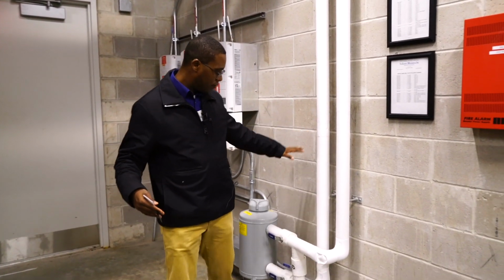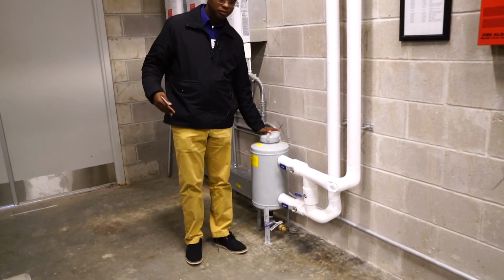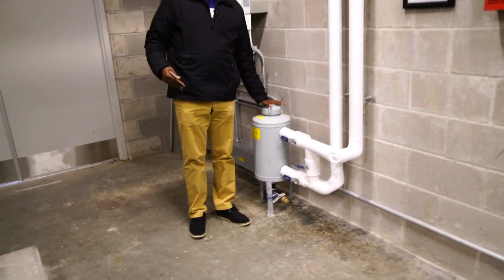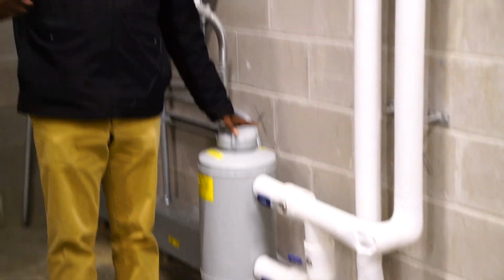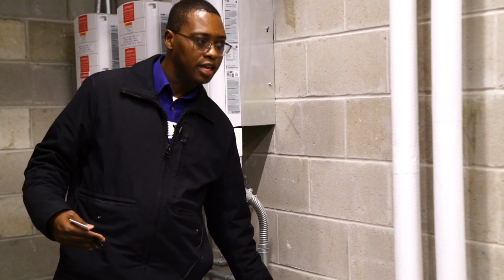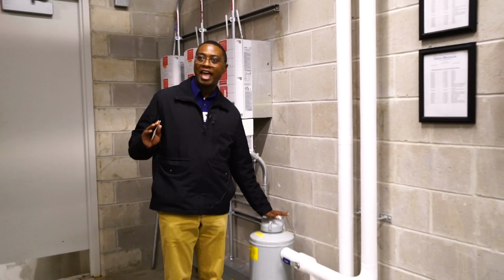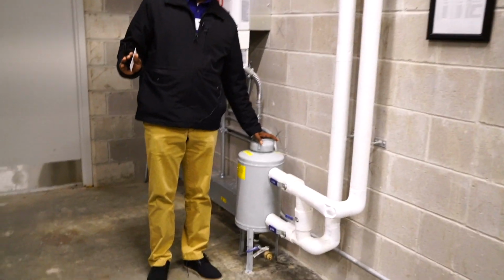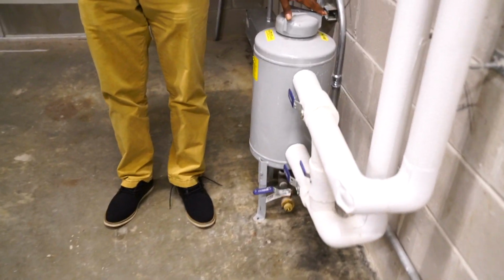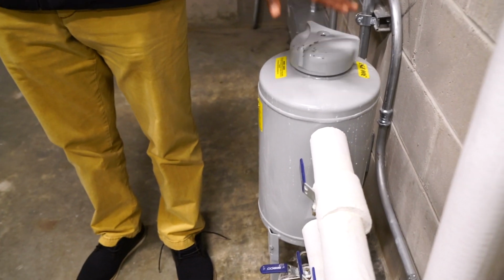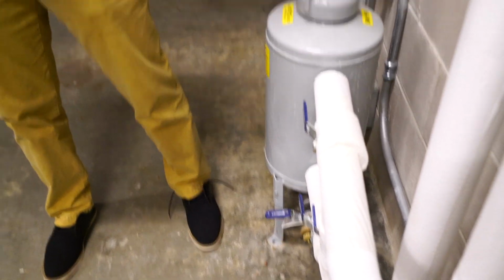So right here what you have is a chemical bypass feeder. This is a manual feed. My service tech will come in and add a chemical here, called F600. That's the name we give it. It's a nitrite-based chemical for your hot water heat system, to protect it and minimize corrosion. That's basically what you have.